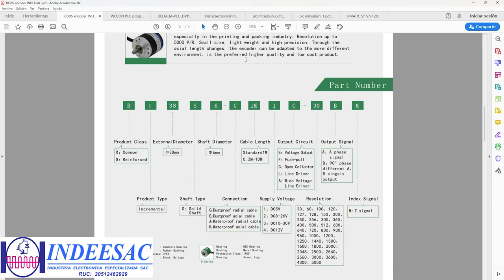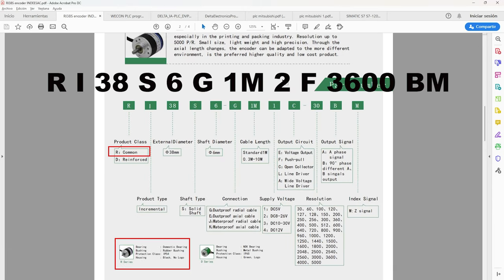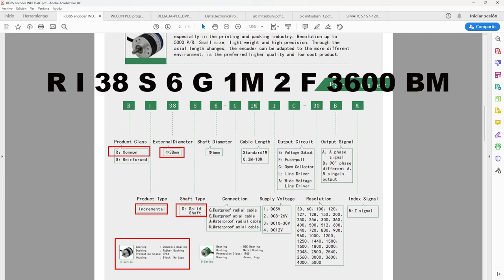The encoder type means R for common product meaning a classic material. I is an incremental encoder. 38 is its external diameter. S is solid shaft. 6 is its shaft diameter in millimeters. G is dustproof radial cable.